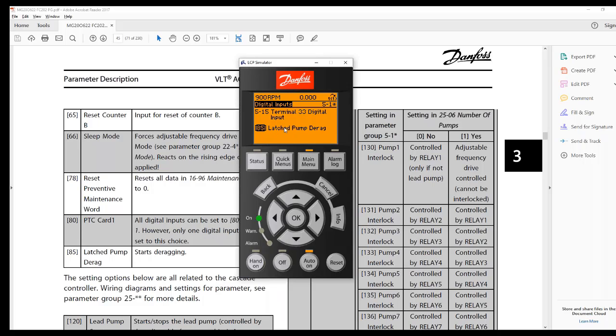So it says latch. So it's like a latch start because once it's triggered, it's going to run the DERAG. So when this goes on, it will. Let's see how it acts. So there, I turned that on. I turned it on terminal 33. So I'll just hit 33. So no, I have to give it a start at the same time. It's telling me. Okay. So I have that. I don't have two jumpers here.